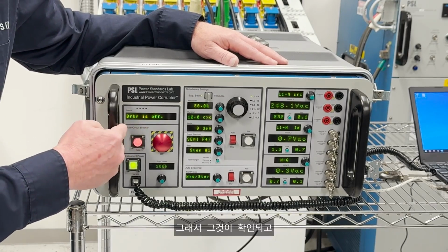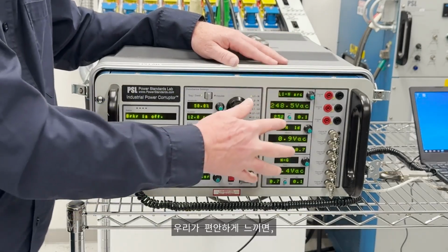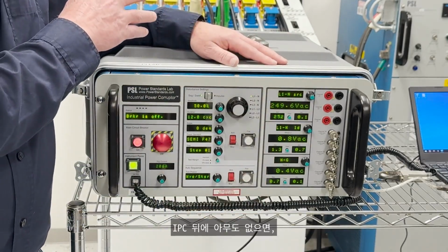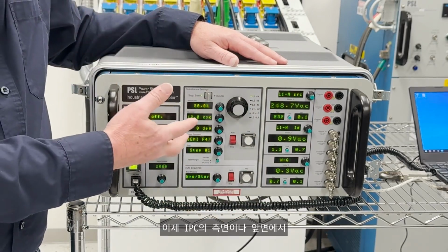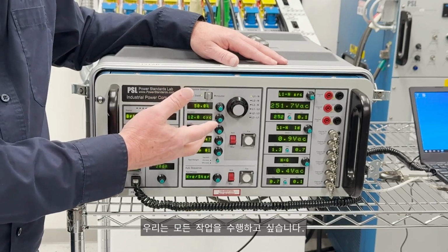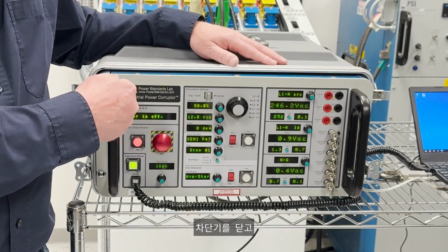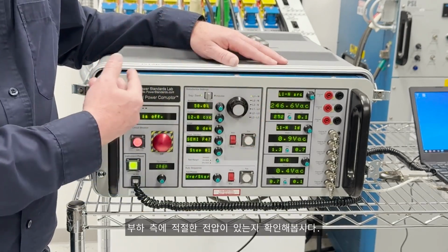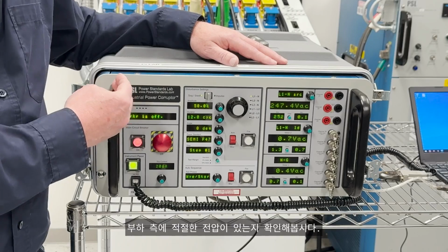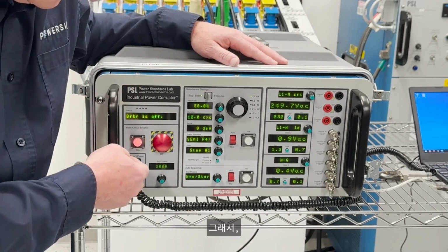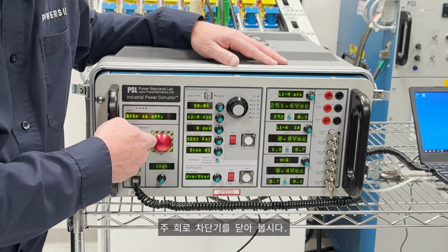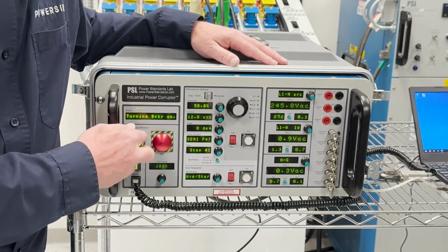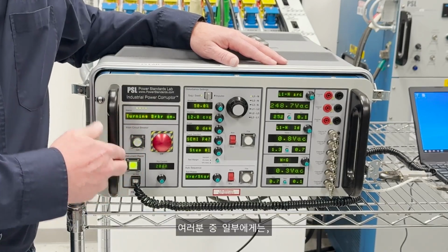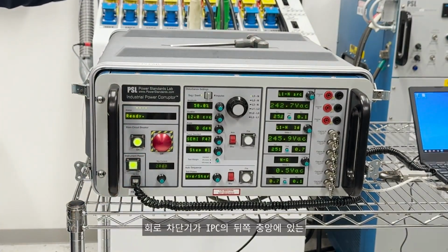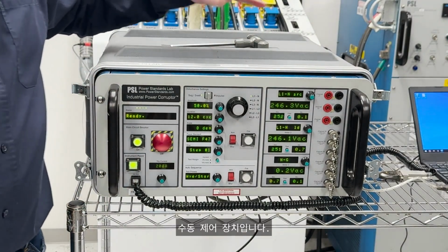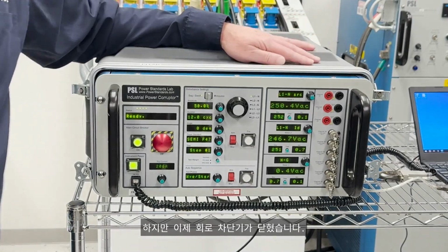So with that being validated, with us being comfortable, nobody behind the IPC, we want to do all the operation now from the side or the front of the IPC. It would be time to close the breaker and see if we have an appropriate voltage on the load side. So with that, let's close the main circuit breaker. And for some of you, the circuit breaker is a manual control at the center and the back of the IPC, but this has now closed the circuit breaker.